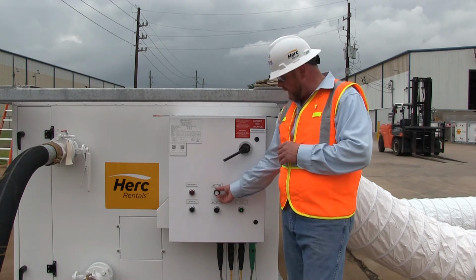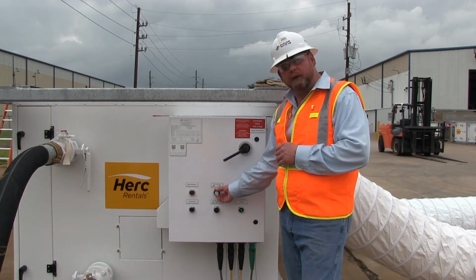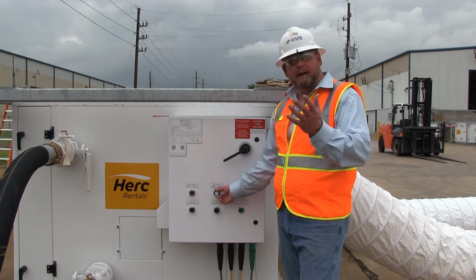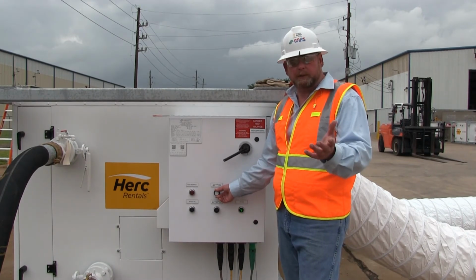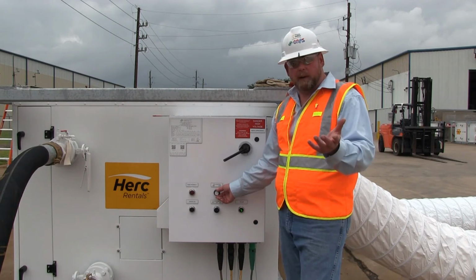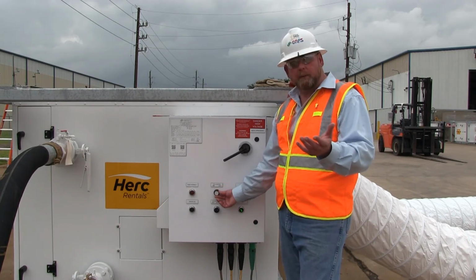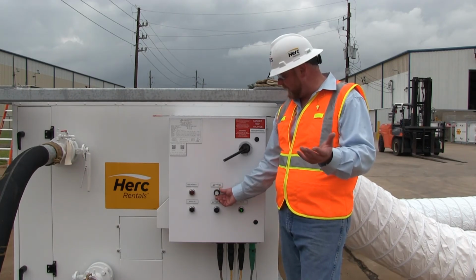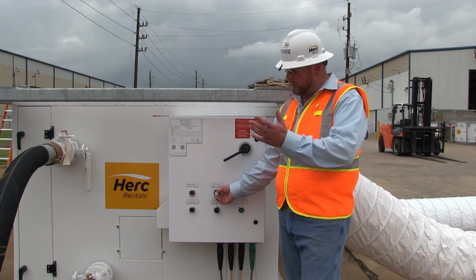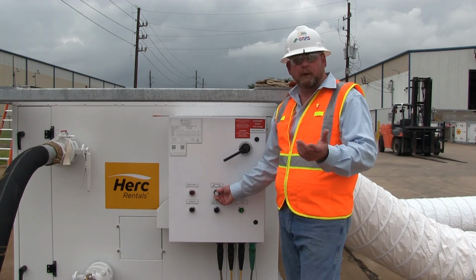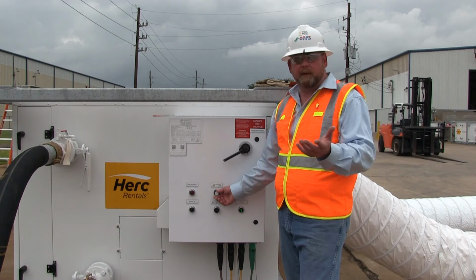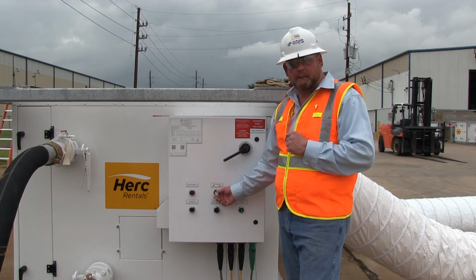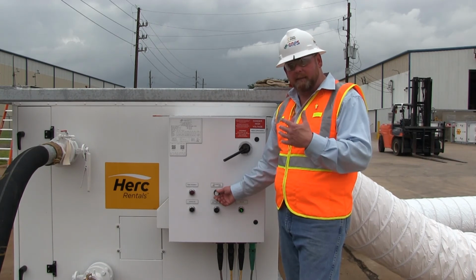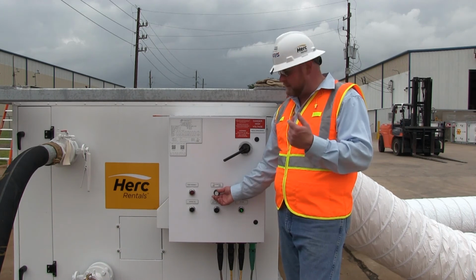You've got a potentiometer here that goes from min to max. And this is how you turn the airflow up on that. You can adjust this by whatever the job requires, static pressure-wise or by temperature-wise. This will increase your air to the right, which is where the max sticker is here now, or back down to the minimum. Now we're at full speed. The machine can run 6,000 CFM at 5.5 inches of static pressure. It's winding up now, and it simply balances it.